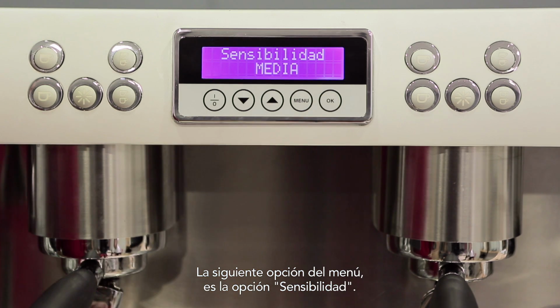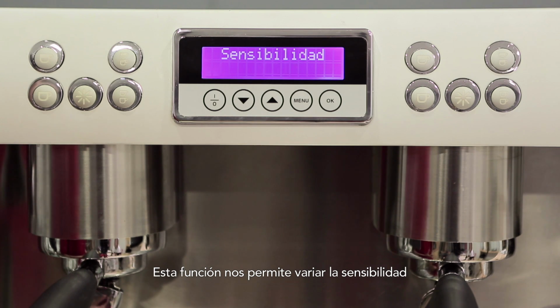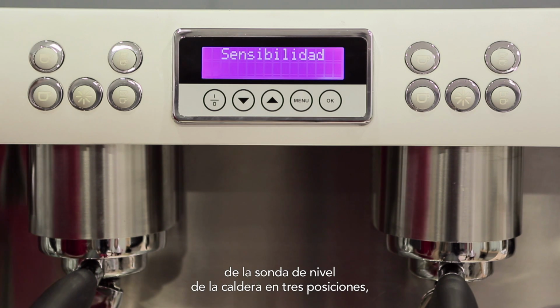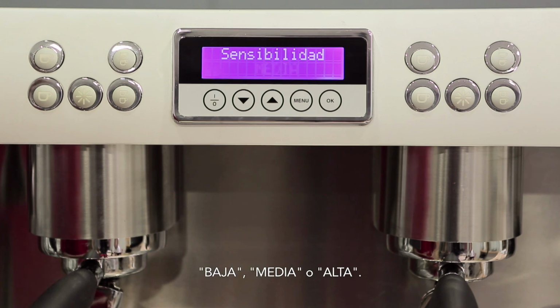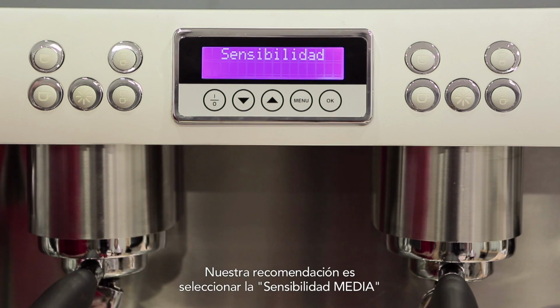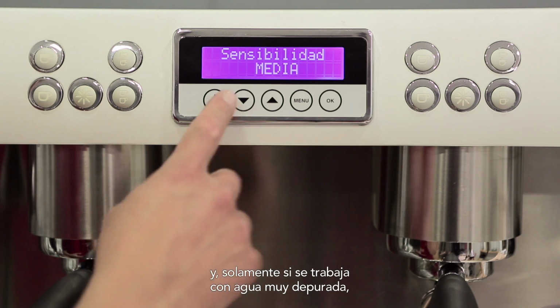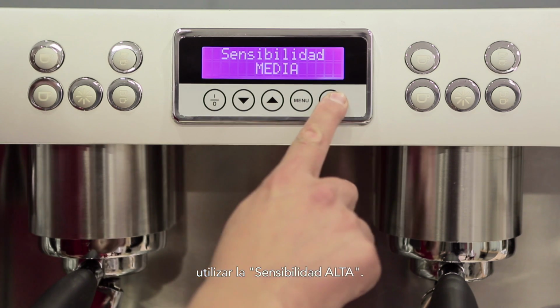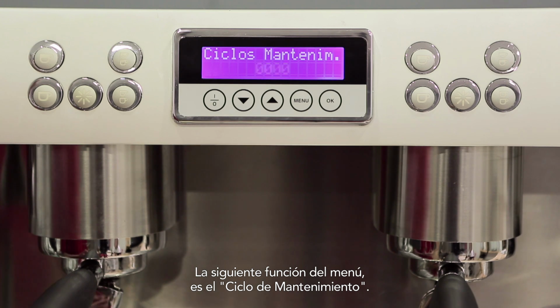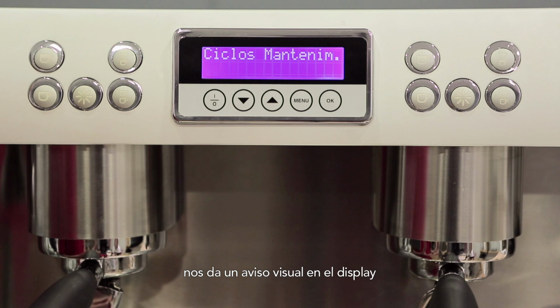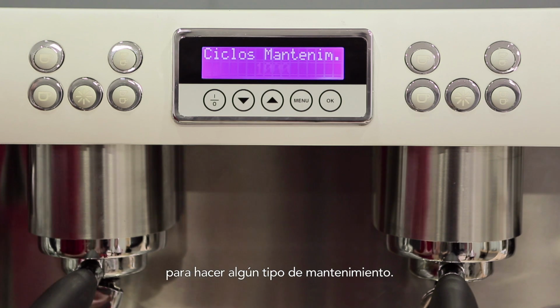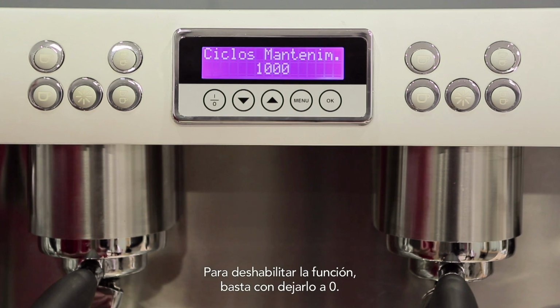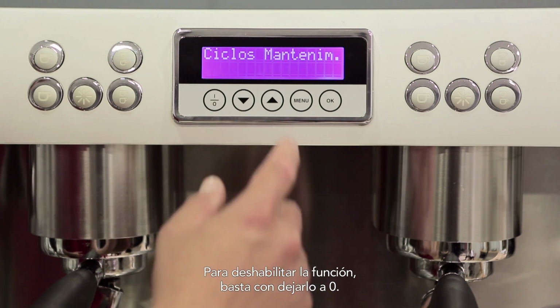The next option in the menu is the Sensitivity option. This function allows us to vary the sensitivity of the level probe of the boiler in 3 positions, low, medium or high. Our recommendation is to select medium sensitivity and only if working with highly purified water to use high sensitivity. The following function of the menu is the Maintenance Schedule. It tells us the number of services for which the machine will flash up a visual warning on the display to perform some kind of maintenance. To disable this function, it's sufficient to set it to 0.